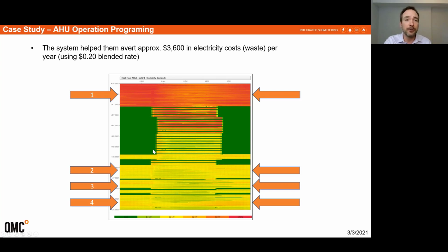The M&V consultants we were working with contacted us later to dive further into the data because this load was not operating properly overall. When we started drilling into the data again, you could see that at some point a manual override was done to the system, and it was operating at medium intensity, this time from midnight to midnight over the weekends, completely off schedule. This was alerted to the staff, and they made changes to get it back into operating condition. What we really like about heat maps is their ability to use interval data to quickly see the performance of a load over an entire year if necessary and optimize its use, so you can get good energy savings once you're alerted to what's happening at the property.